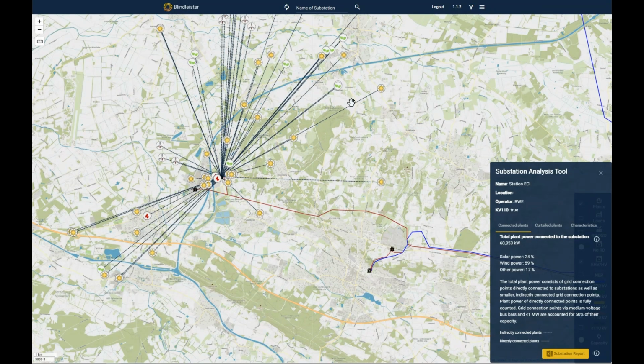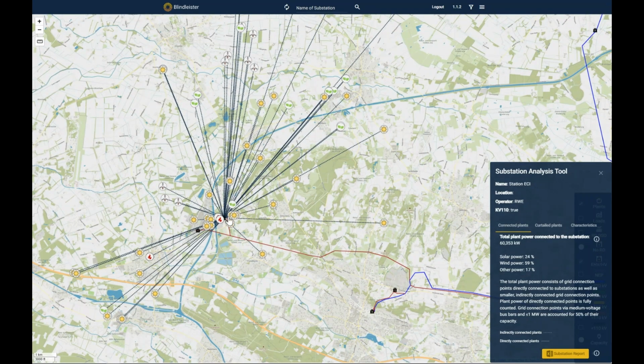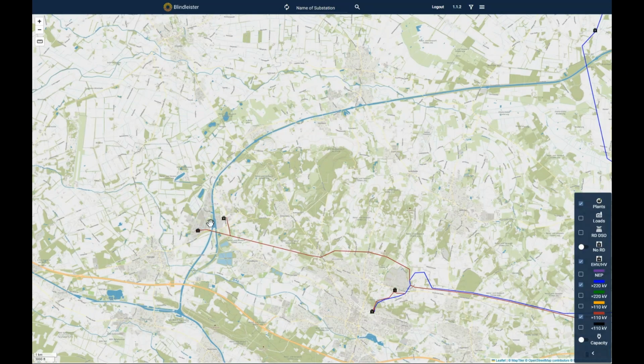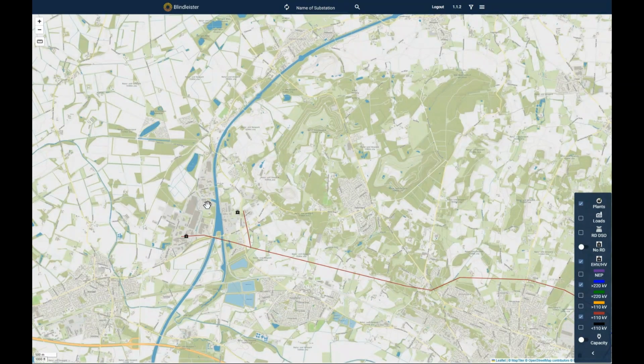So it can be a sink, a load sink, but we can also have excess generation, which is up to 35.5 megawatt. So we have to include here an export of energy of roughly 35 megawatt. This is 68, 35, so we get up to 105, 110 megawatt, which means we can assume a battery storage not more than like 20 megawatt that we are building here, and this is already optimistic.